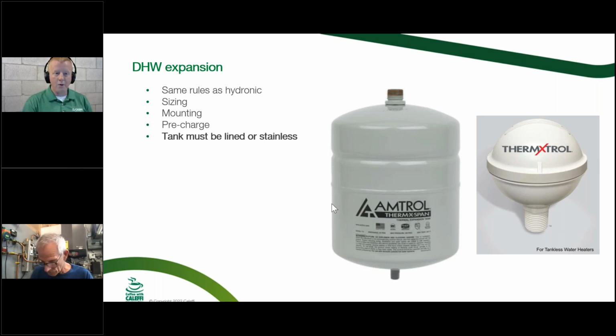Okay, now from there though, one thing that a lot of people don't consider is that sometimes in your area you might not require a backflow, but you require a pressure reducing valve. And a pressure reducing valve, ironically and inadvertently, does almost the exact same thing as a backflow preventer by allowing water through it, but not backwards. So the big thing there is if you do have a pressure reducing valve, you've got to make sure that you have an expansion tank on there too, to accommodate that expansion even without a backflow preventer. So these tanks will typically have a 3/4 connection on the top instead of 1/2, so that's how you can recognize them as different from a thermal expansion tank.